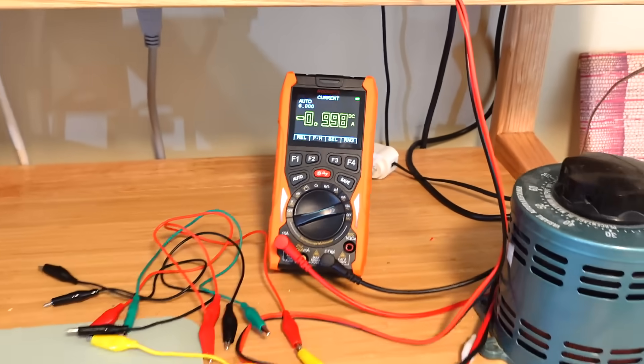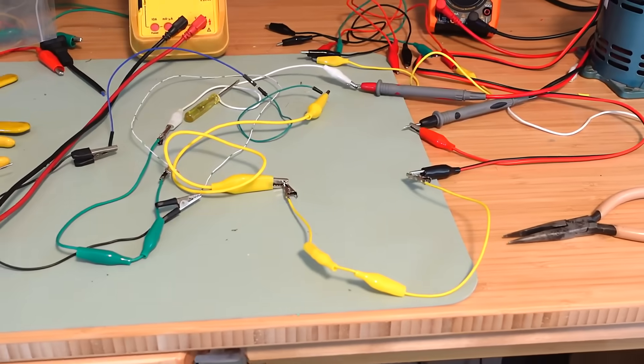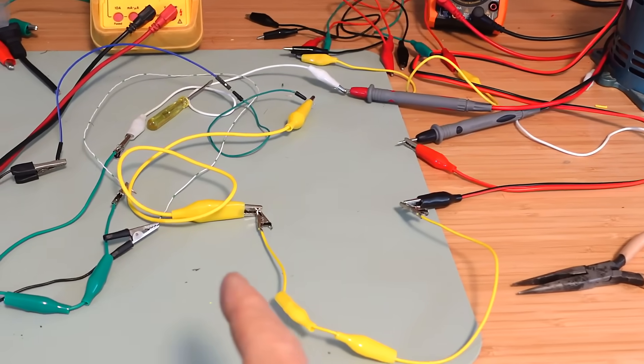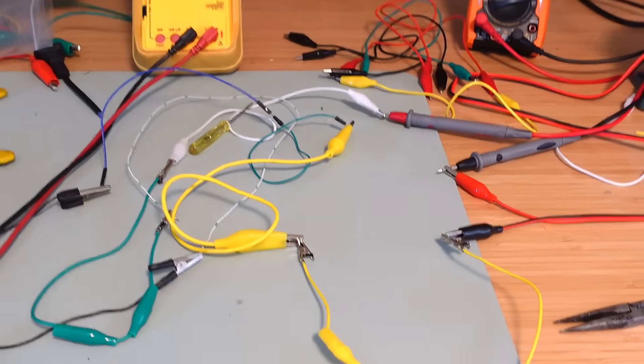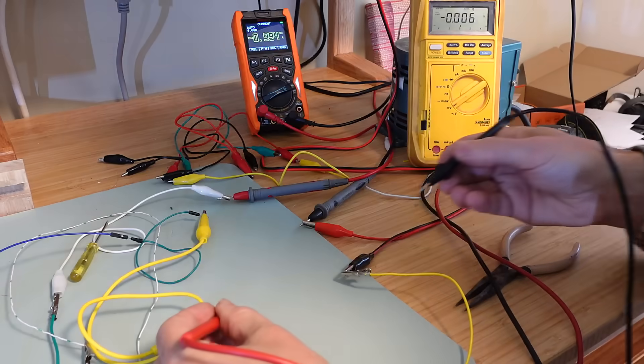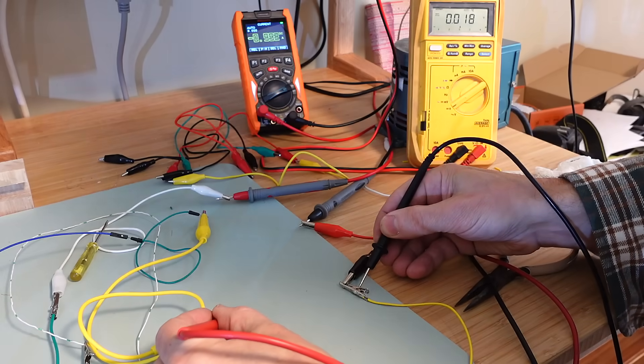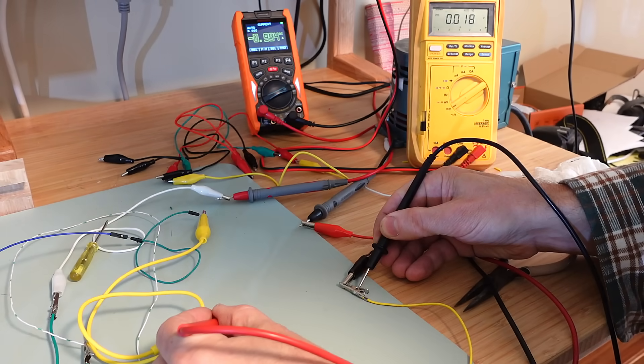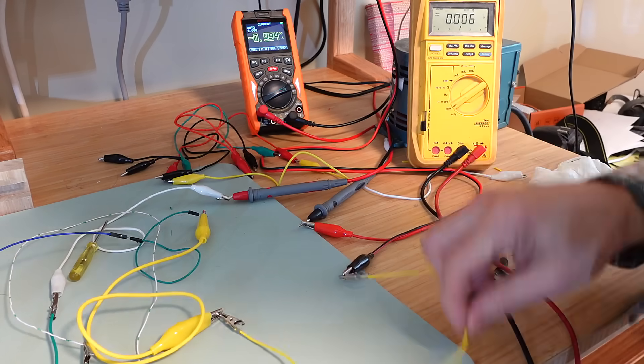Now with a 1 amp current going through all of my leads. Now, let's just get warm, but basically each ohm will be 1 volt across. So, I can just check that with another voltmeter. The yellow lead now reads 18 millivolts. So, it probably has 18 milliohms.